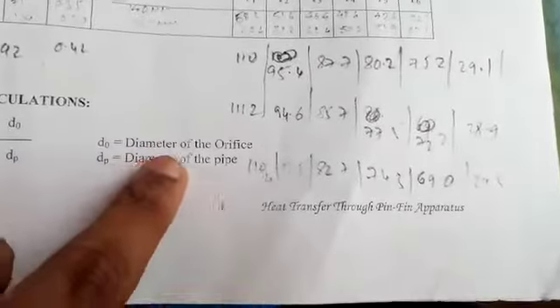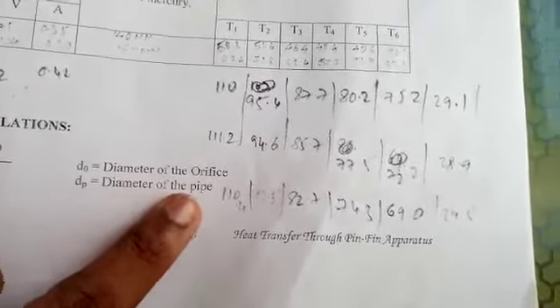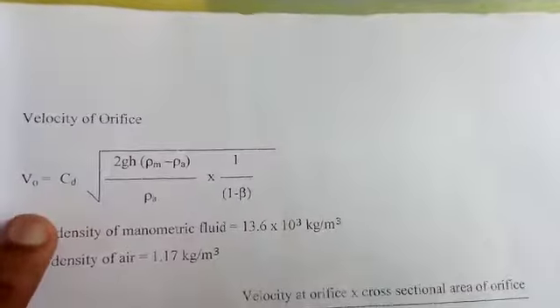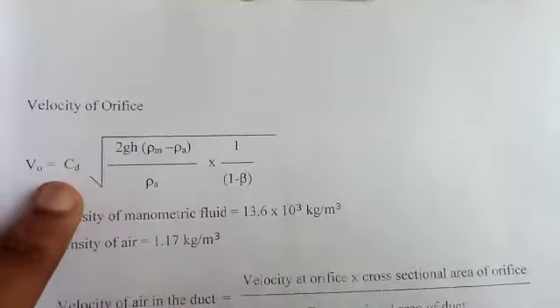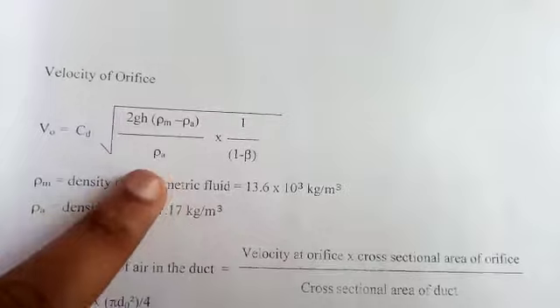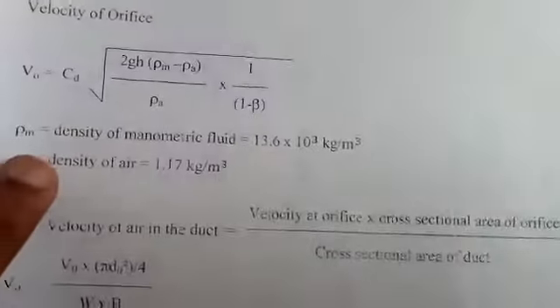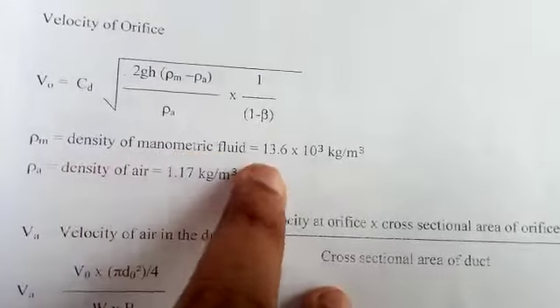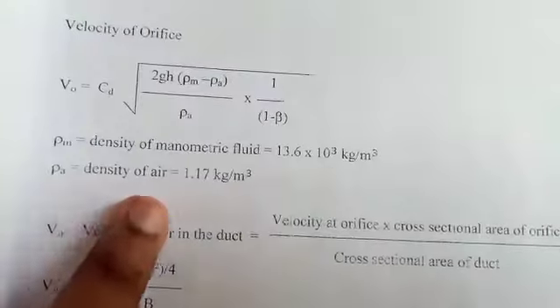Coming to calculations: beta (β) = d₀ / Dp, where d₀ is the diameter of the orifice and Dp is the diameter of the pipe. The velocity at the orifice V₀ = Cd × √(2gh × (ρm − ρa) / ρa) × 1 / √(1 − β⁴), where ρm is the density of the manometric fluid = 13.6 × 10³ kg/m³ and ρa is the density of air = 1.17 kg/m³.